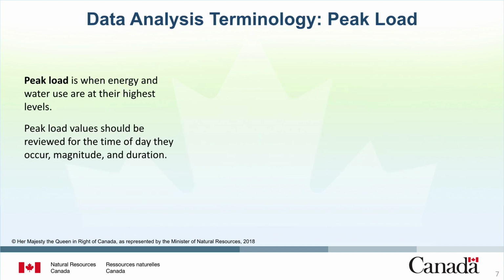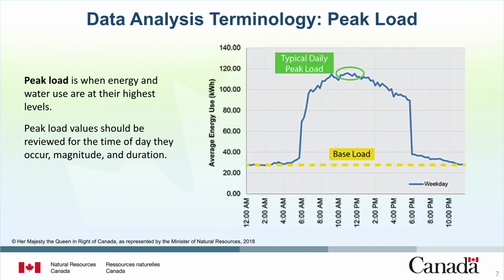The next term is peak load. Peak load is the load period when energy and water use are at their highest levels. Peak load values should be reviewed for the time of day they occur, magnitude, and duration. The graph is of a load profile, with time on the x-axis and average energy use on the y-axis. The peak load is where the graph is at its highest on the y-axis, which is around noon, where energy use goes to almost 120 kilowatt hours.